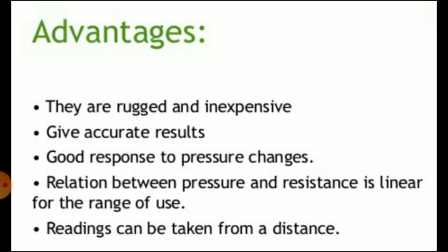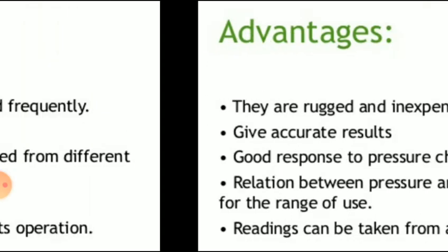Now the advantages of the Pirani gauge. Pirani gauges are rugged, inexpensive, and usually more accurate than thermocouple gauges. It gives a good response to the pressure changes. The relation between pressure and resistance is linear for the range of use, and readings can be taken from a distance.